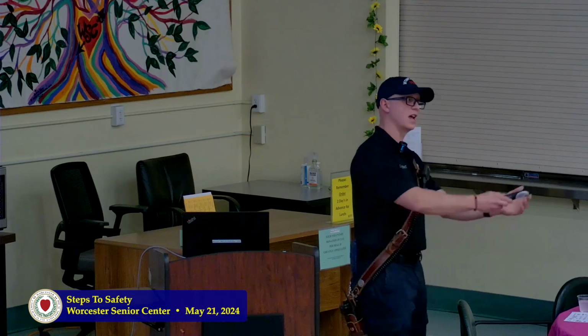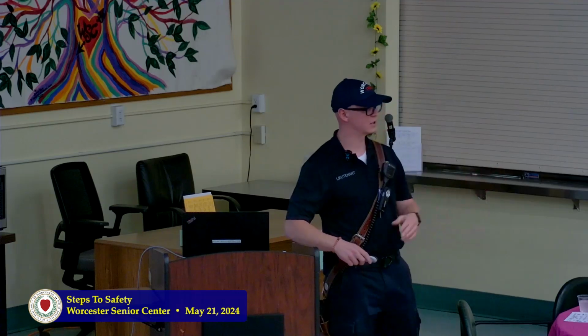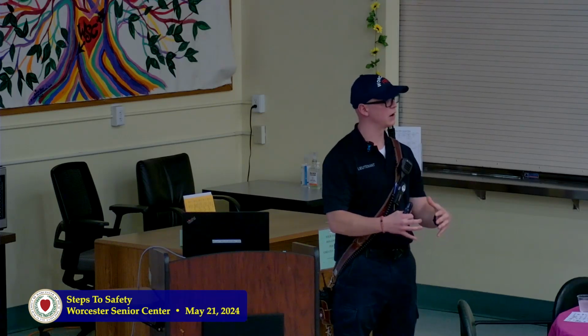So as opposed to everybody coming out of the building, especially if it's an assisted living or a senior facility, instead of getting everybody out for usually what's going to be a false alarm, it's a lot easier for everybody to just shelter in place, and you shouldn't be getting all that fire travel in a high-rise building because of all the fire protection. Do you know if your building is sprinklered? Yeah, exactly. So the chances are that's going to contain the fire. It's going to just be contained to that apartment. So that's why you would shelter in place in a building like that.